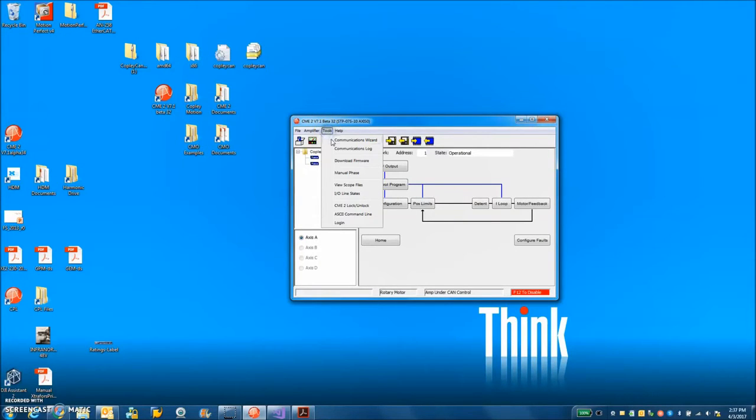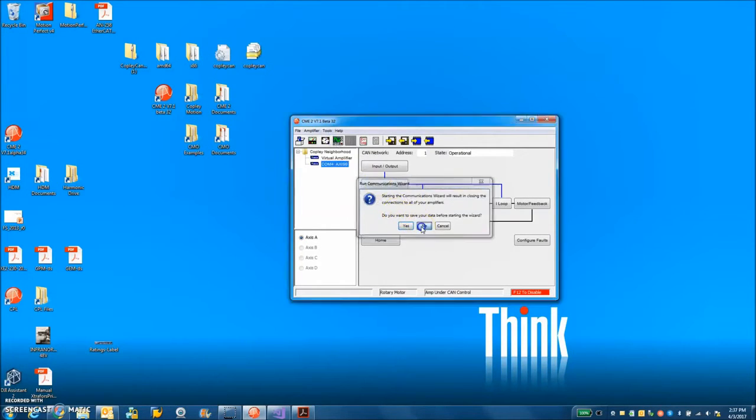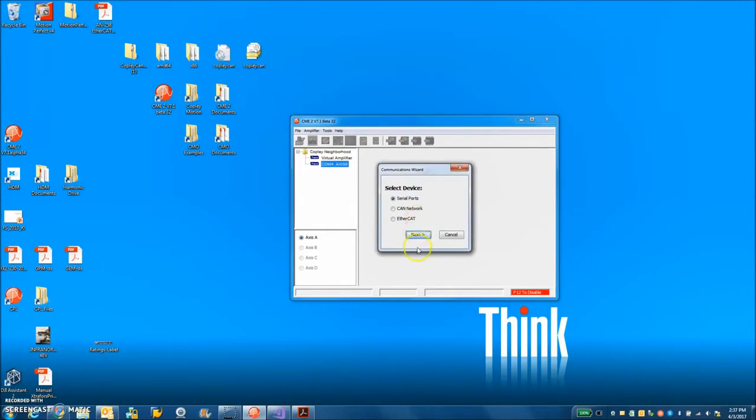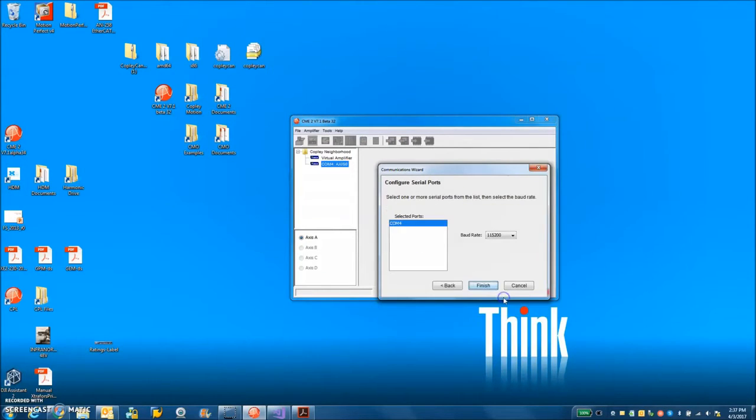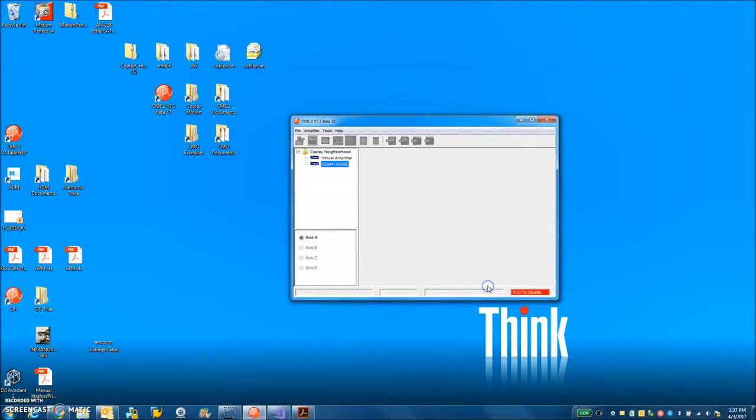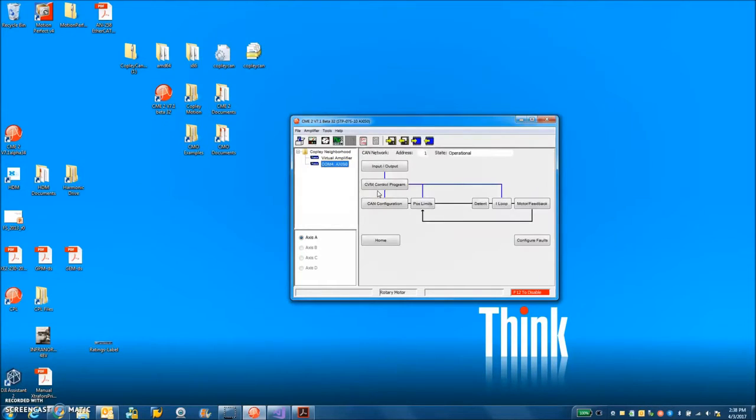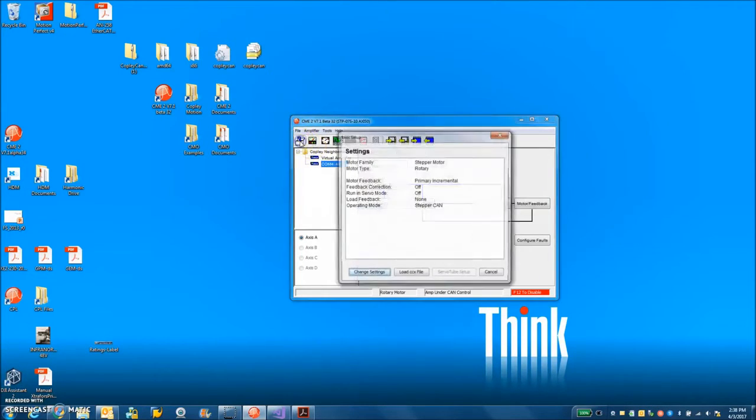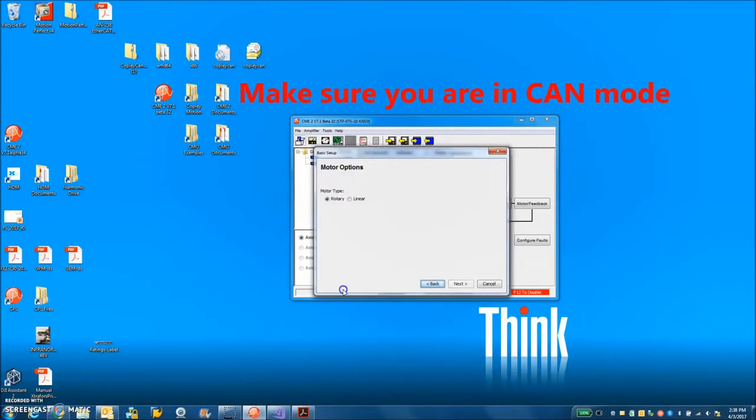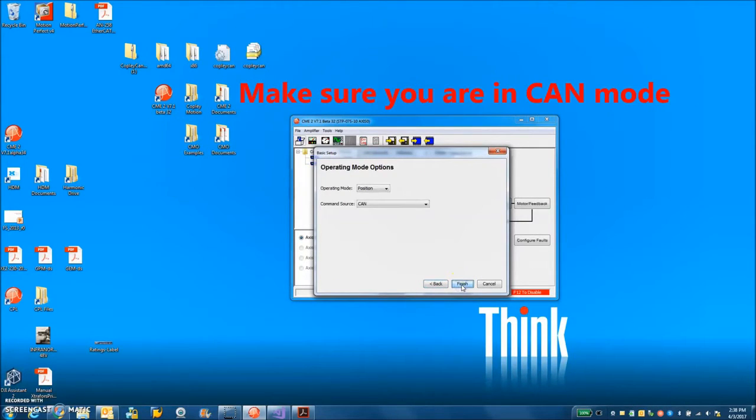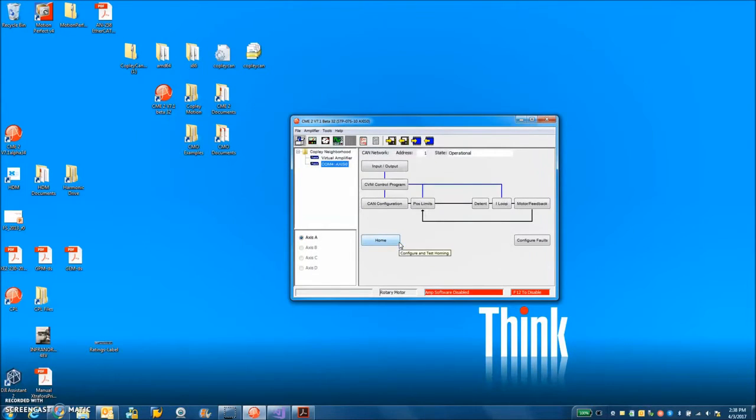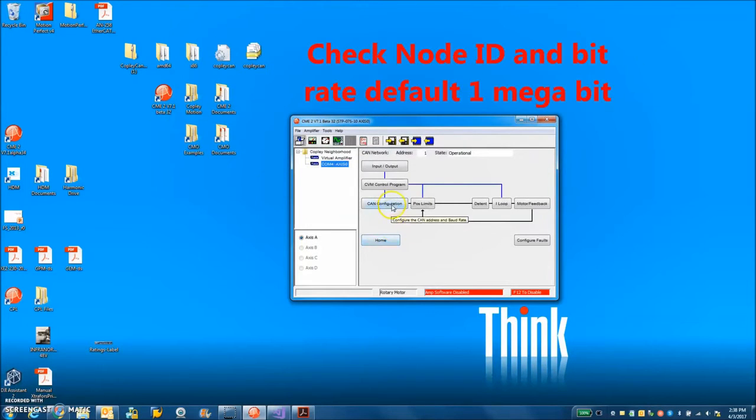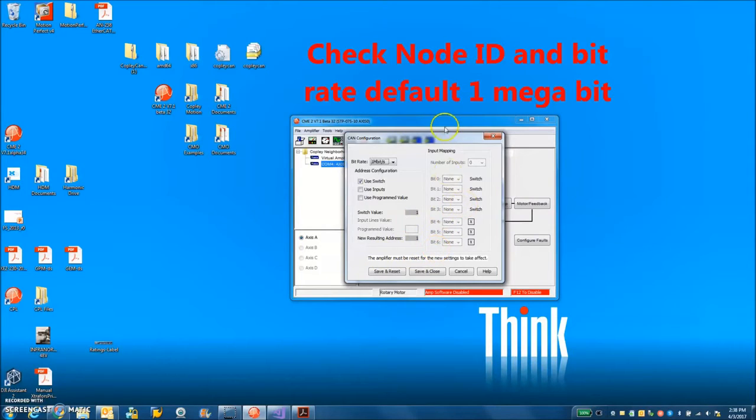So I'm going to use tools communication wizard. I'm going to connect over my serial port first. Pick my COM port. Connects to the drive. And normally in the beginning you'll be asked about the mode of operation. So this is a rotary with encoder position CAN mode. And we can check the CAN configuration. I have the switch set to 1.